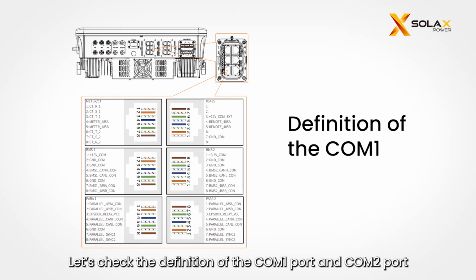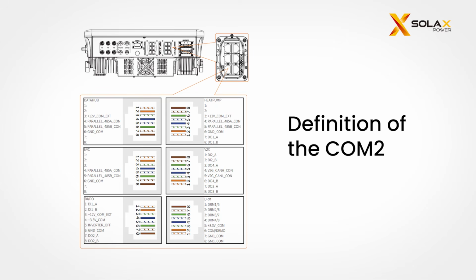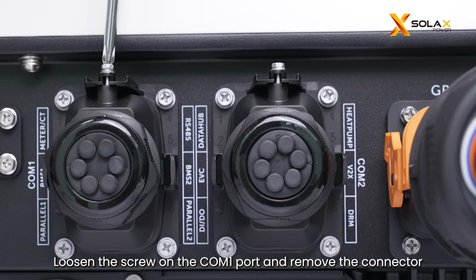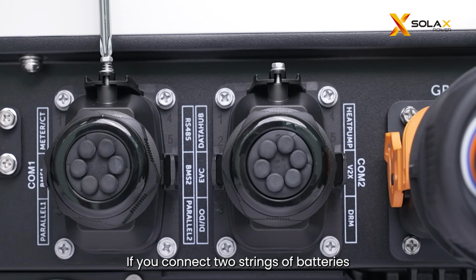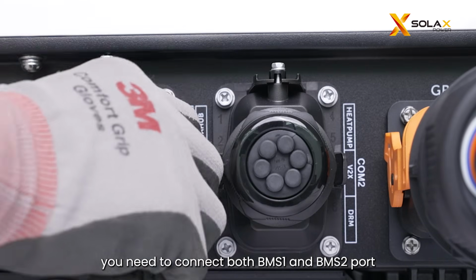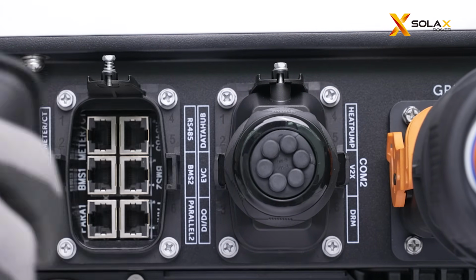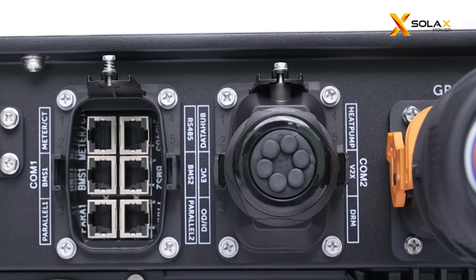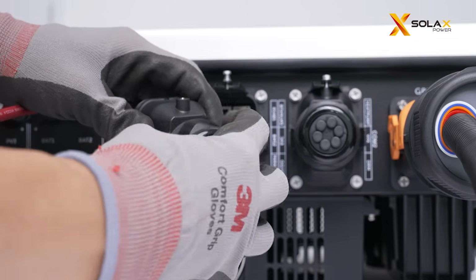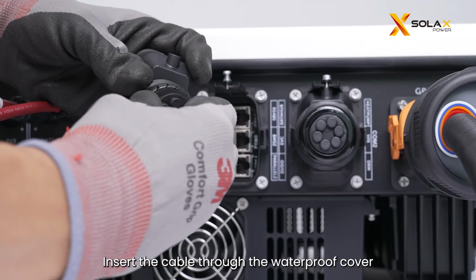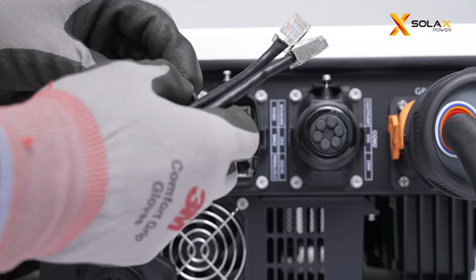Let's check the definition of the COM1 port and COM2 port. Loosen the screw on the COM1 port and remove the connector. If you connect 2 strings of batteries, you need to connect both BMS1 and BMS2 port. Insert the cable through the waterproof cover.